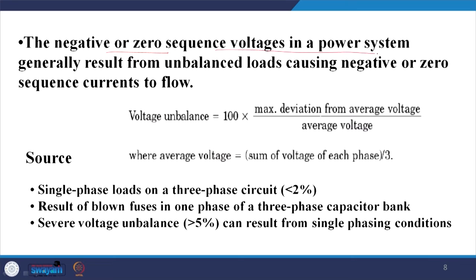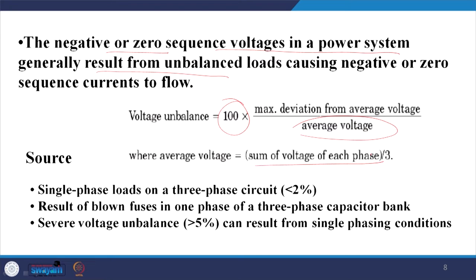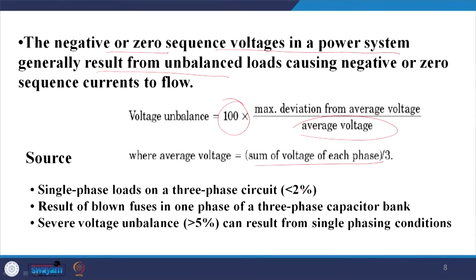Zero sequence voltage in a power system generally results from unbalanced loads, causing negative or zero sequence current to flow. Voltage unbalance equals 100 percent times the maximum deviation from the average voltage, divided by the average voltage. Generally, we accept a condition where the negative sequence is less than 2 percent.